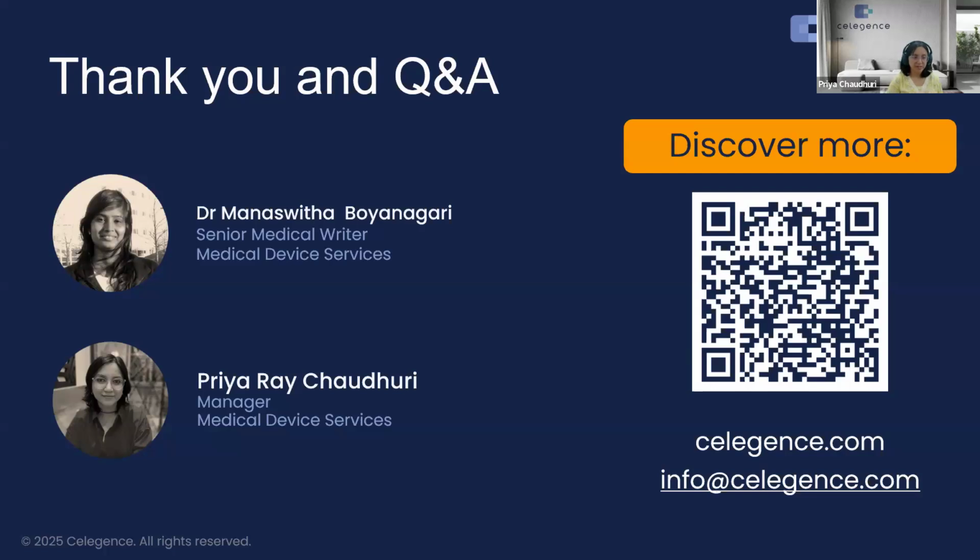Yeah, so let's say our claim is the survival rate is high or higher than some kind of benchmark devices, definitely the literature that we should look out for is comparative literature. The equivalent device is a different story. If we are claiming equivalence, definitely we have to look out for literature on the equivalent device. But if we are talking about similar devices or competitors, definitely we have to go for the primary comparison that we have at the end, a conclusive statement in the CER: the benchmarking that we have from the similar devices in comparison with the data of the device in question.